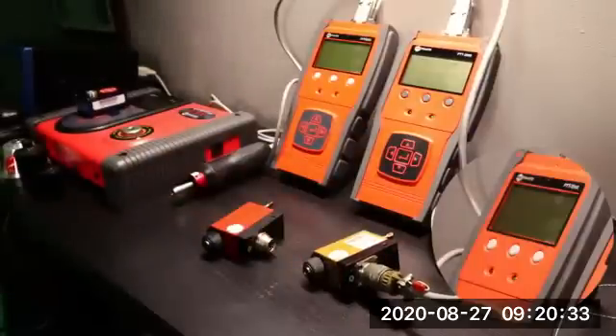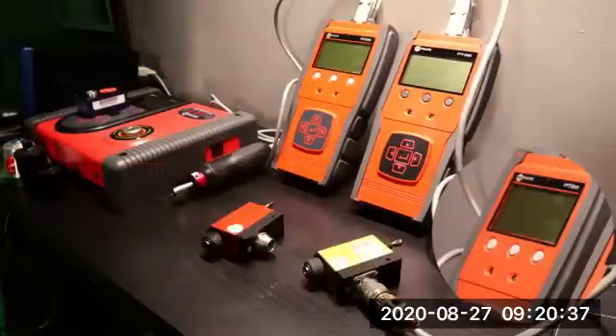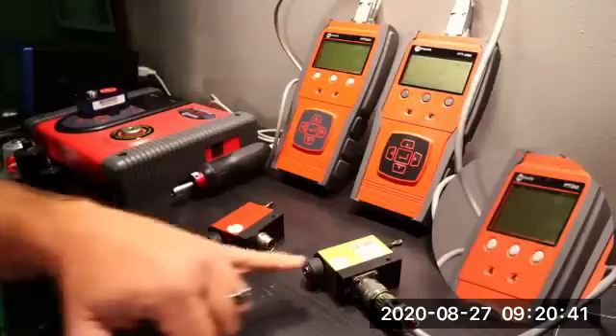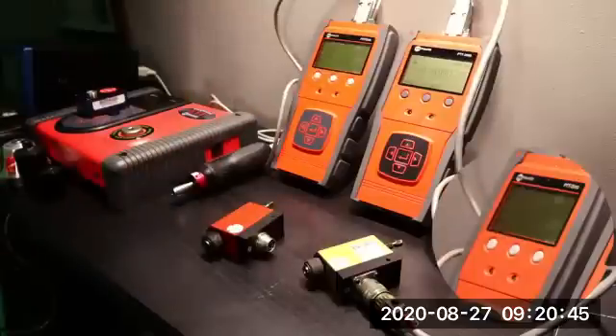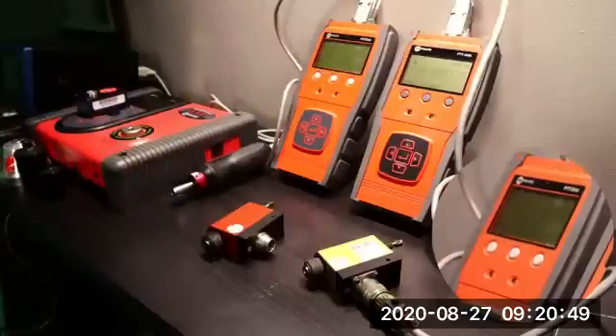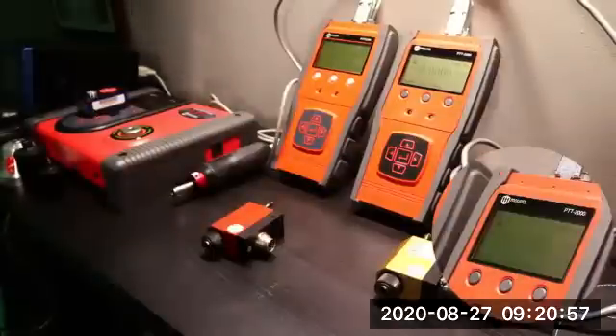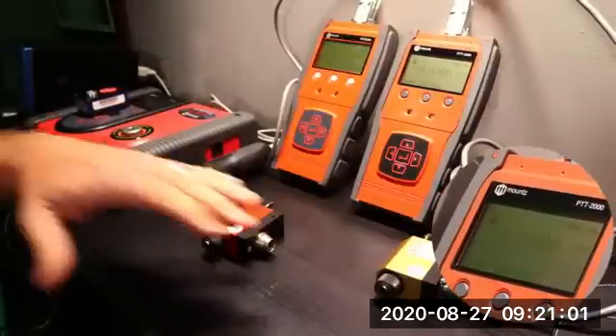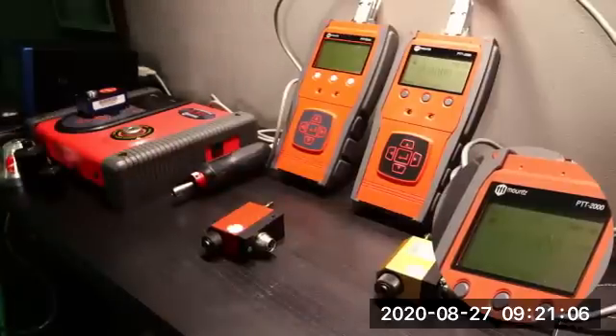Now, one of the features we have with our rotary sensor is the ability to store our calibration data in the sensor itself. You may have seen it on the display. So the calibration data is stored within the sensor. This gives us the ability to monitor that our sensors are staying within the calibrated range of the date intervals. We recommend that you have your sensors and analyzers calibrated on either a 6-month or 12-month interval to make sure you're following the guidelines of your torque program.